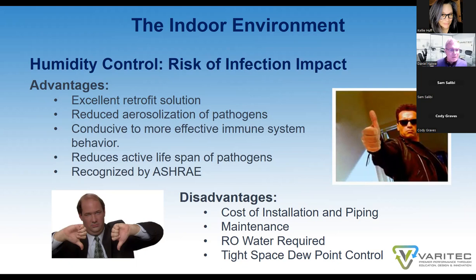They reduce the aerosolization rate of pathogens. They are conducive to more effective immune system behavior. Properly humidified environments reduce the active lifespan of pathogens and are a solution for creating more risk-free environments, per ASHRAE. The disadvantages are the cost of installation and piping, the maintenance program to keep humidification systems in operation, and RO water is required. And also we have to make sure that building dew points are adequately controlled to prevent condensation from occurring.